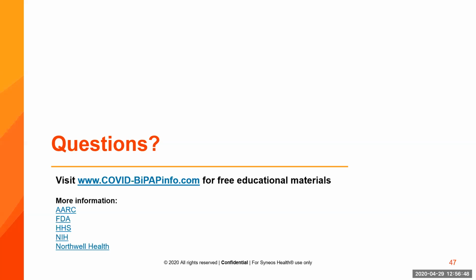The next question. I see you are using HEPA filters on the exhalation port of the circuit and at the machine. Can just viral filters be used in those areas? Yeah, I'll take that. That's a yes and no answer. The HEPA filters will last close to 24 hours. They're hygroscopic also, and they hold a lot more volume than the typical viral filters that you might see on the inspiratory limb of these ventilators. So yes, they can be used.